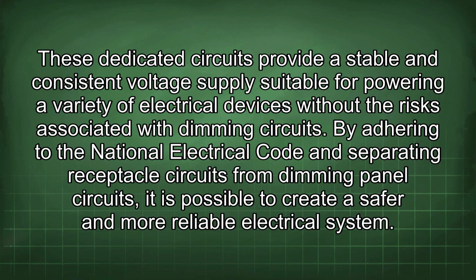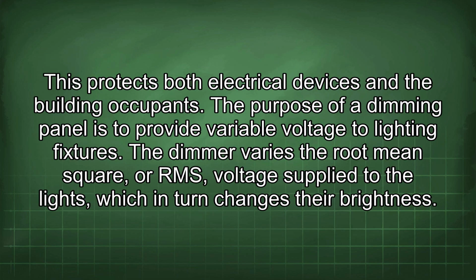By adhering to the National Electrical Code and separating receptacle circuits from dimming panel circuits, it is possible to create a safer and more reliable electrical system. This protects both electrical devices and the building occupants. The purpose of a dimming panel is to provide variable voltage to lighting fixtures. The dimmer varies the root mean square, or RMS, voltage supplied to the lights, which in turn changes their brightness.